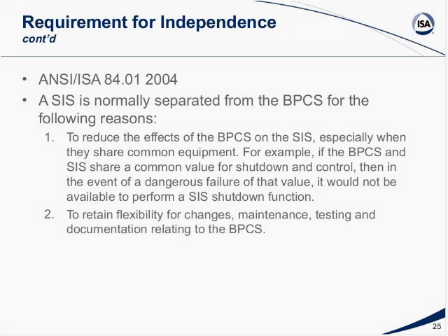Now, when they did a revision of IEC 61511, which is the ISA 84, when that revision was made in 2004, it did not require a shutdown. This is what it says in there. A safety instrument system is normally separated from the control system for the following reasons: to reduce the effects of control in the safety system, especially when they share common equipment. For example, if the control system and safety system share a common valve for shutdown and control, then in the event of a dangerous failure of that valve, it would not be available to perform safety shutdown functions. To retain flexibility for changes, maintenance, and testing, documentation related to the basic process control system.